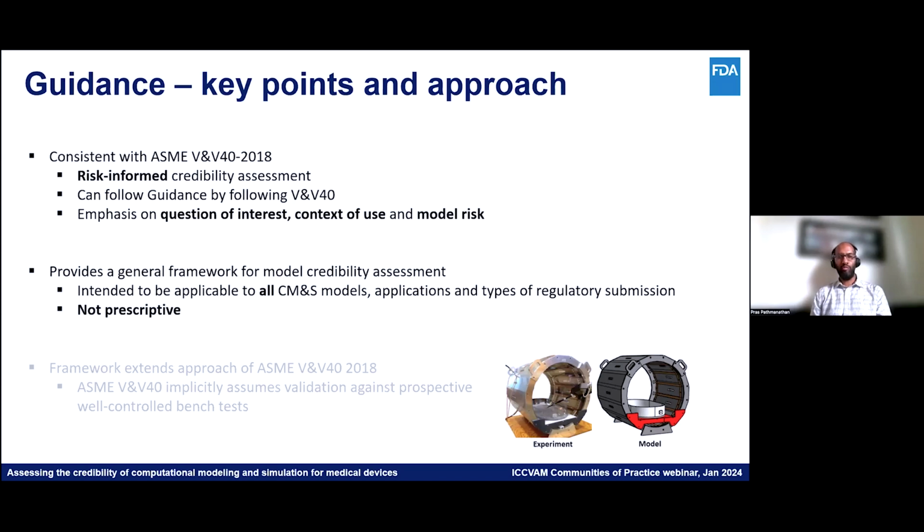It provides a general framework for evaluating computational models, assessing credibility, and it's intended to be applicable to all first principles based models. So anything that's not standalone statistical data driven. So a wide range of modeling fields from solid mechanics, fluid flow, electromagnetism, thermal, physiological models of any kind of physiological system, such as the heart or the cardiovascular system. It's intended to be applicable to any kind of application.